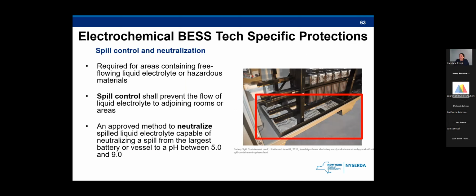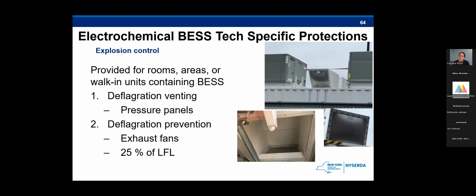So here is the explosion control requirement that is necessary for all battery types. So this is kind of when you see lithium ion utilizing exhaust ventilation. So explosion control can really be handled in 2 separate ways. We have the deflagration venting, which utilizes pressure panels. And then if there's enough built up gas pressure in the unit, it will push open the panels and release the gas. So most lithium ion systems will have deflagration venting panels that will manage the overpressure or blast wave that is produced in an explosion if there is one.